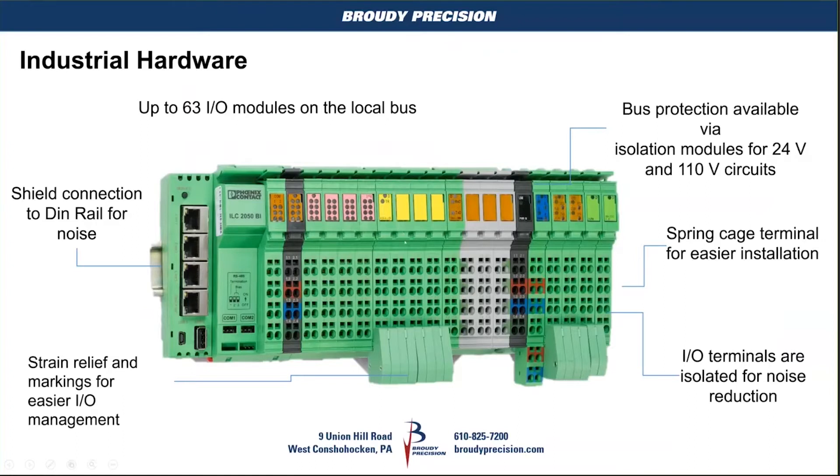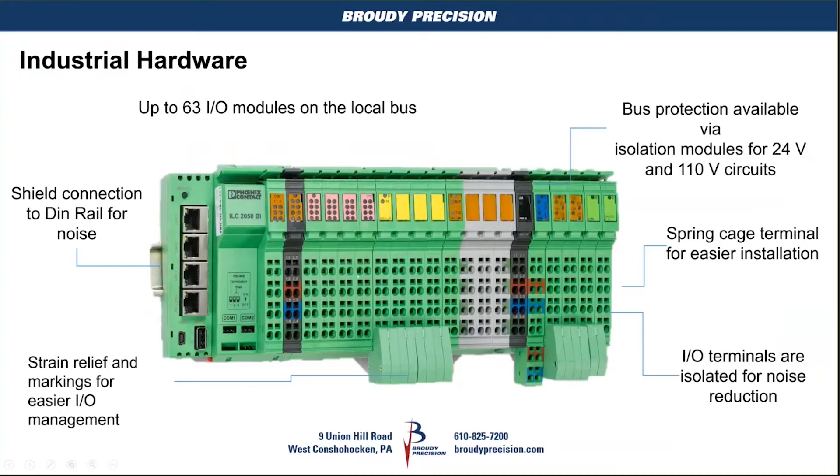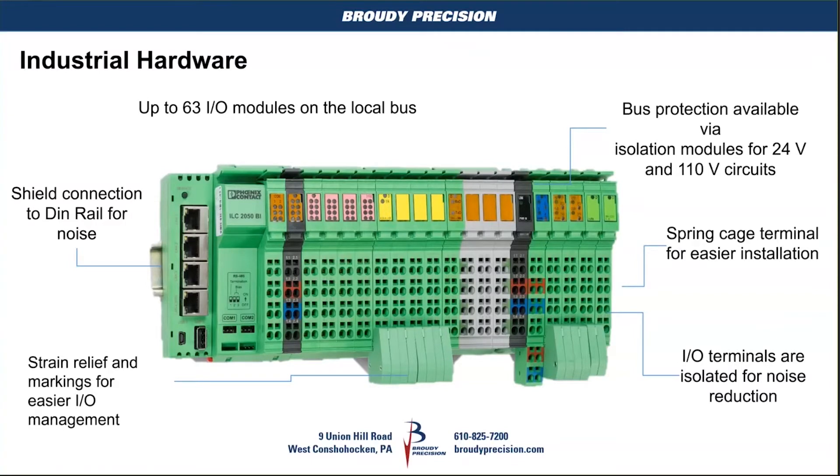Within that footprint, you've got roughly 20 to 30 points of IO in that small footprint. It depends on IO cards because some of the IO cards have two points, others have four, some have eight depending on the IO. And it doesn't matter what position they're in.